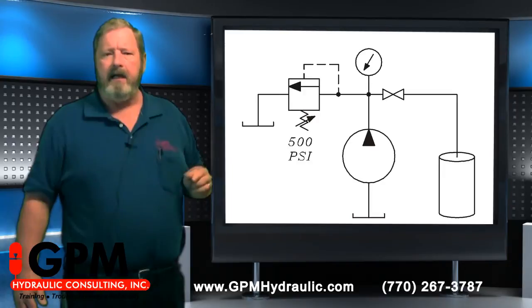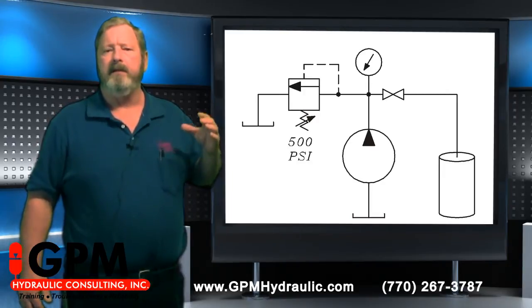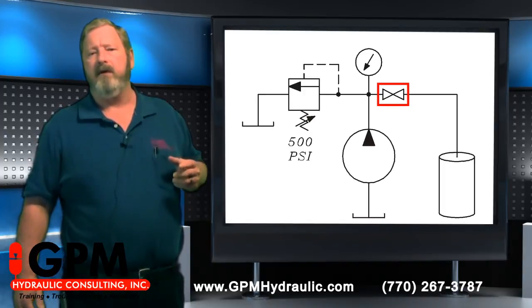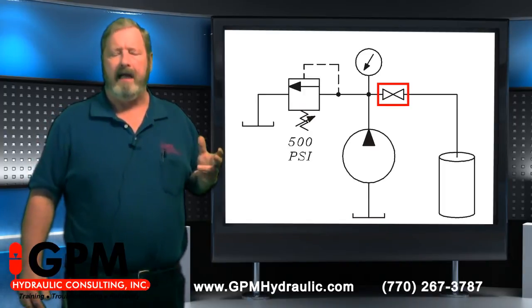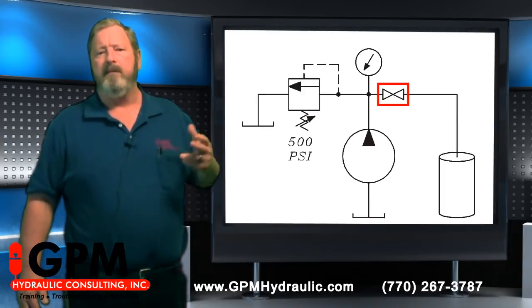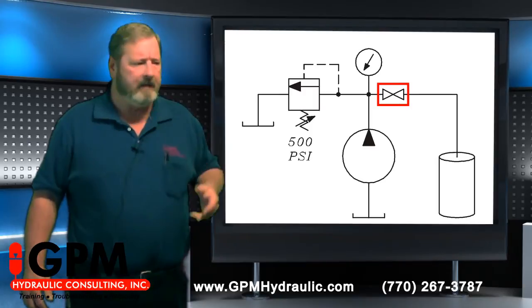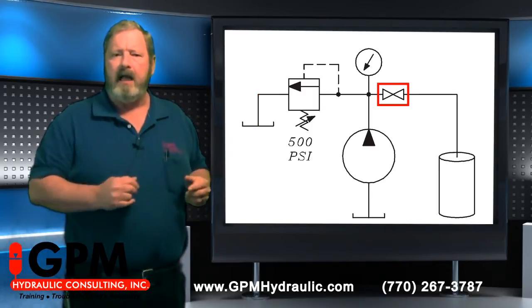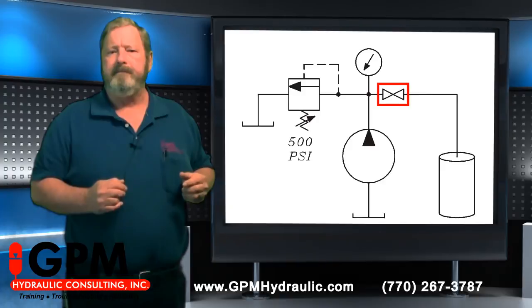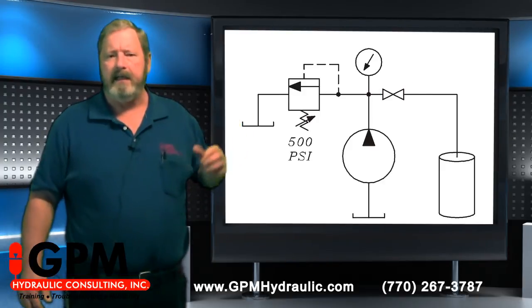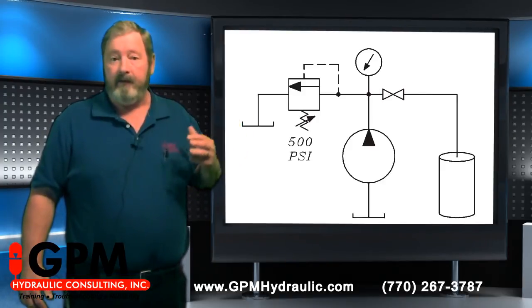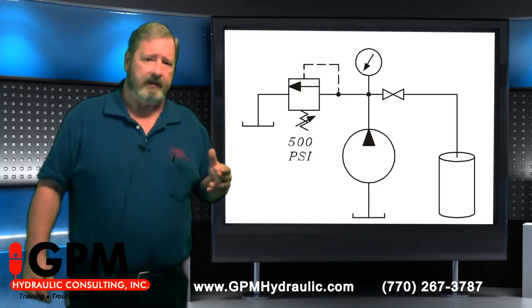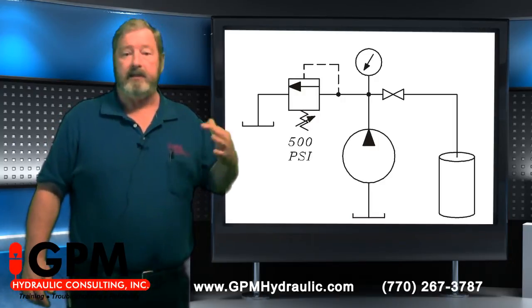Let's follow it in the other direction. We get to this component that looks kind of like a bow tie. This is a symbol for a manual valve — a hand valve, usually a ball valve or a gate valve. It's open because the symbol is not filled in. When the symbol is not filled in, that means it's open, and whenever the manual hand valve is open, it adds no resistance to the system — it's as though it's not there.